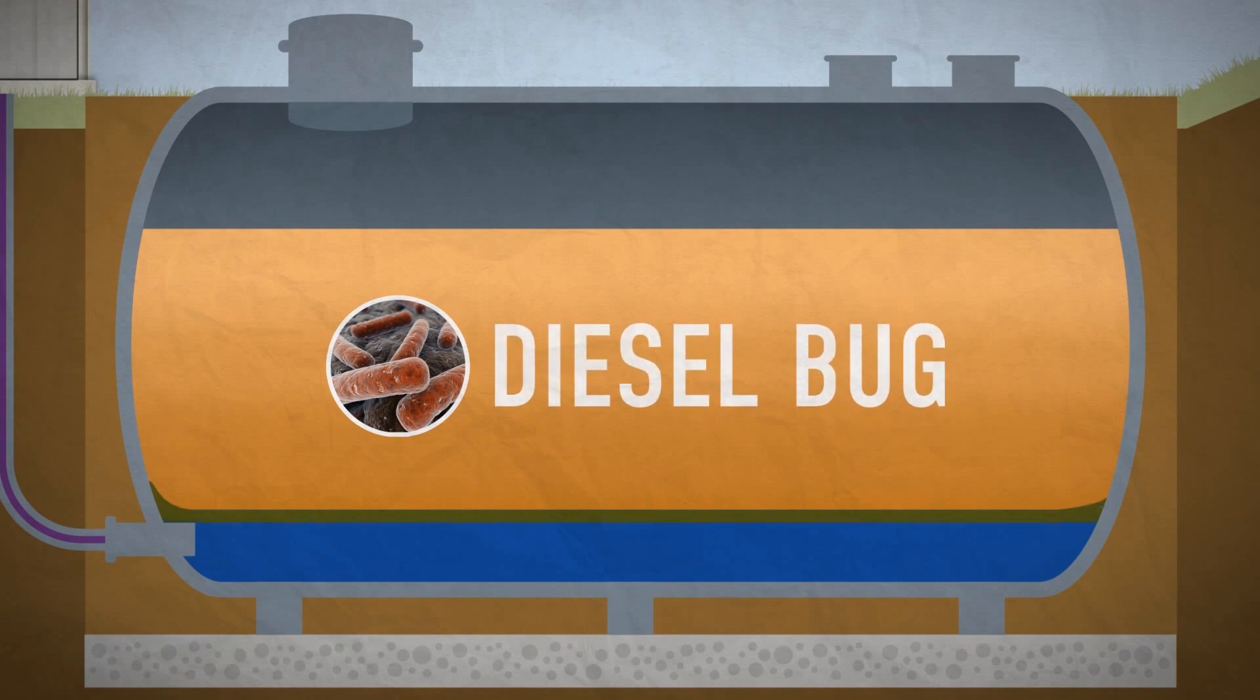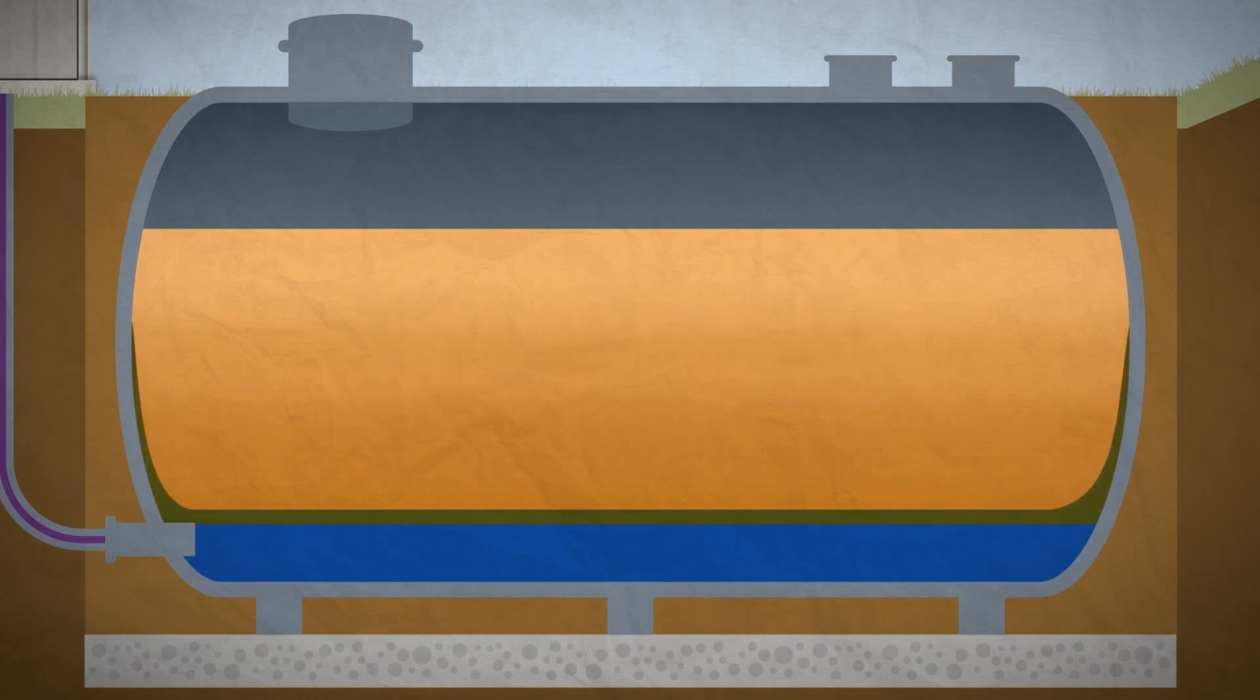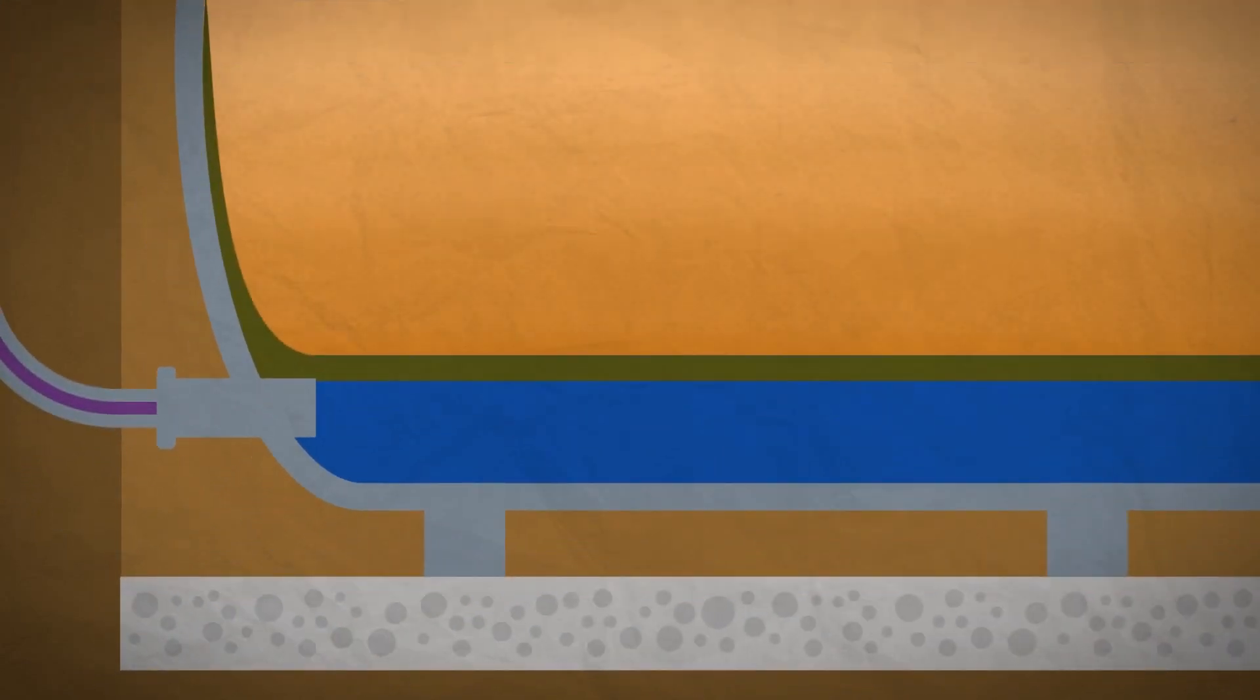Diesel bug is the generic term given to microbial growth in diesel. It occurs when bacteria feeds on the hydrocarbons in the fuel and multiply in the water. As a result, the bug usually grows in the rag layer, the point at which fuel and water meet.